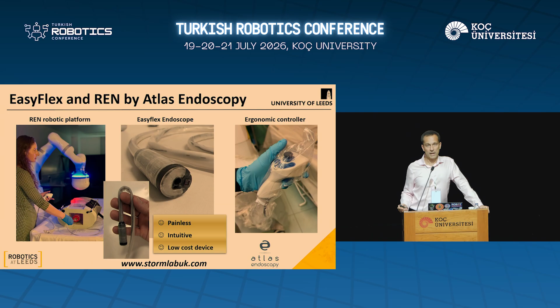The key point of this platform that makes it work is localization. When we talk about magnetic manipulation of medical devices inside the body, I always stress that localization is crucial for closed-loop control and intelligent magnetic manipulation. The core IP that we have in our company is real-time localization that I developed when I was at Vanderbilt University. It basically uses a magnetic field sensor and an inertial sensor at the tip of the endoscope. The magnetic field sensor measures the field generated by the external magnet at the tip of the endoscope. Then with the inclinometer, we rotate the vector into the frame of the external magnet, and we do a search in a pre-calculated magnetic field map to get the pose of the tip of the endoscope.